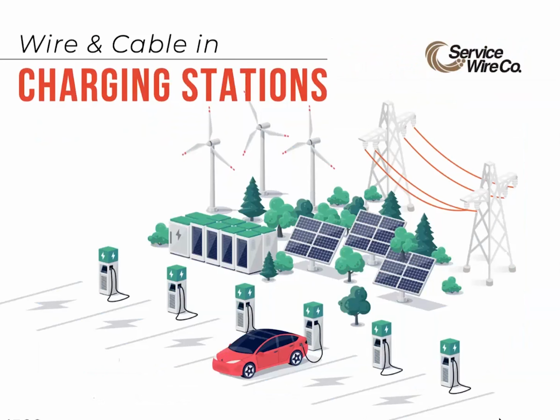Okay, so how does low voltage copper wire and cable fit into the EV charging world? Just like an industrial facility, EV charging stations are powered by either renewable energy, fossil fuels, or utilities. Medium voltage cables connect substations and transformers. Transformers then step this down into low voltage. Service wire's low voltage cable can then be used to connect the switchgear to the individual charging stations. Our cable is typically buried underground in conduit or concrete. We can use ServicePlex, ServicePro X, USE-2 single conductors, and even jacketed type MC armored cable in these installations.